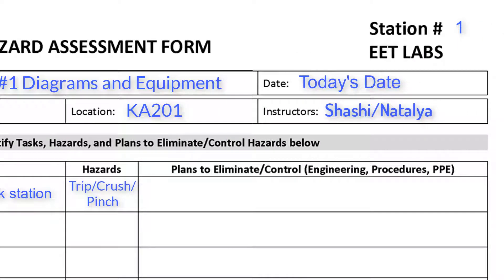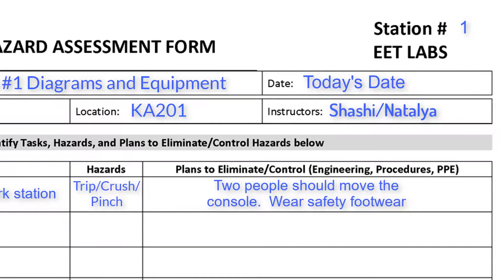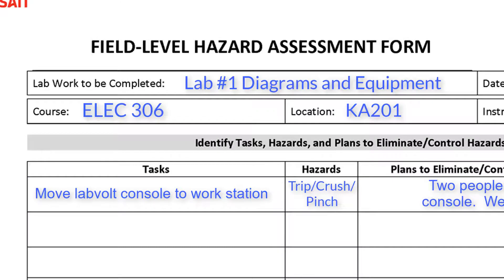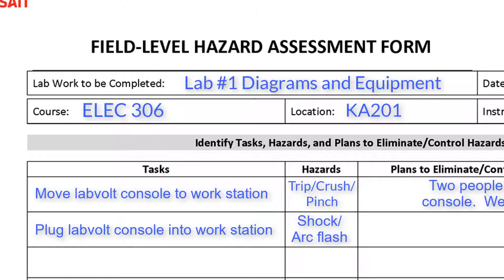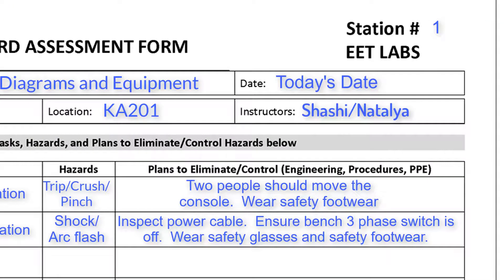Enter the plans to eliminate or control the hazard. In this example, the hazard will be controlled by using administrative and PPE methods of control. Another example of a task is to plug the LabVolt console into the workstation. The hazards associated with this task are shock and/or arc flash. Under plans to eliminate the hazard, inspect the power cable and ensure the three-phase switch is off — these are both administrative types of control. Safety glasses and safety footwear are PPE control.